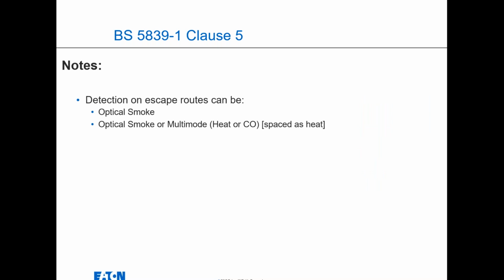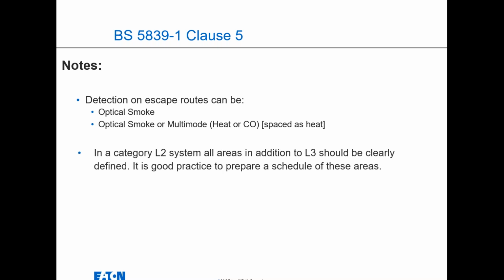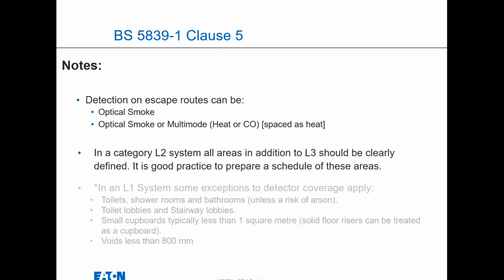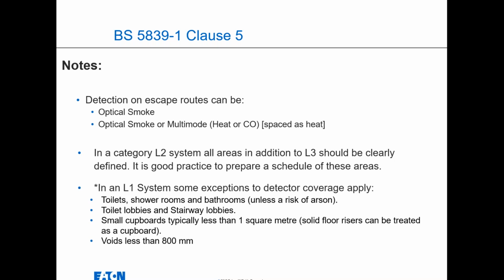So just some notes. The detection types on the escape routes can be optical smokes or optical smokes multi-mode. So that's heat or carbon monoxide, and that is spaced as heats. So you've got to be careful with that. If you're using heat detectors, there's a smaller footprint that they can cover. In the category L2, all areas in addition to L3 should be clearly defined. As I said earlier, it's good practice to get a schedule of those. And an L1 system is everywhere.